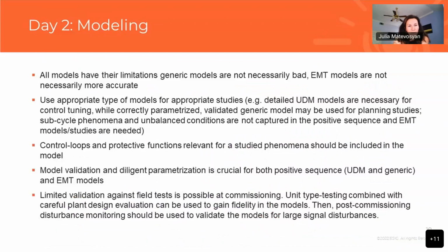Then jumping on to modeling, basically it was pointed out that all models have their limitations, and generic models are not necessarily bad, and EMT models do not necessarily mean more accurate models, that all models need to be correctly parameterized, need to reflect equipment in the field to be a good model. Use appropriate type of models for appropriate studies. Detailed user-defined models are necessary for control tuning, while correctly parameterized, validated generic models may be used for planning studies.